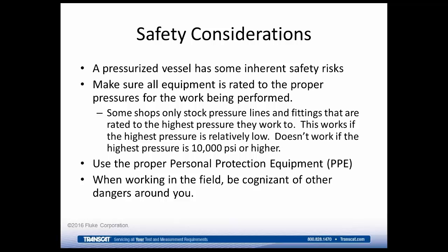You need to make sure you use the proper PPE, or personal protection equipment, such as safety glasses. And when working in the field, be cognizant of the dangers around you. And the safety of the calibration technician should be a key concern when determining if you should do a calibration in the field or back at a laboratory. If the device is installed in a location where it's not safe to do the calibration, then it should be taken back to the laboratory or the shop to do that calibration.